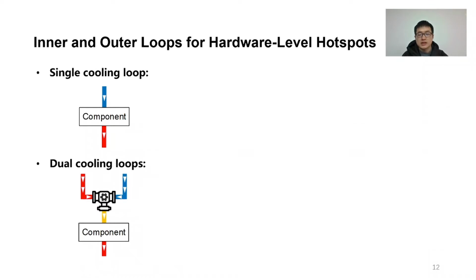The inner and outer loops are designed for solving the hardware-level hotspots. Instead of providing cooling water with the same temperature and flow rate for each hardware component, we design dual cooling loops that provide customized cooling water with different temperature and flow rate. This fine-grained cooling control can significantly reduce the amount of required cold water and save the cooling energy.